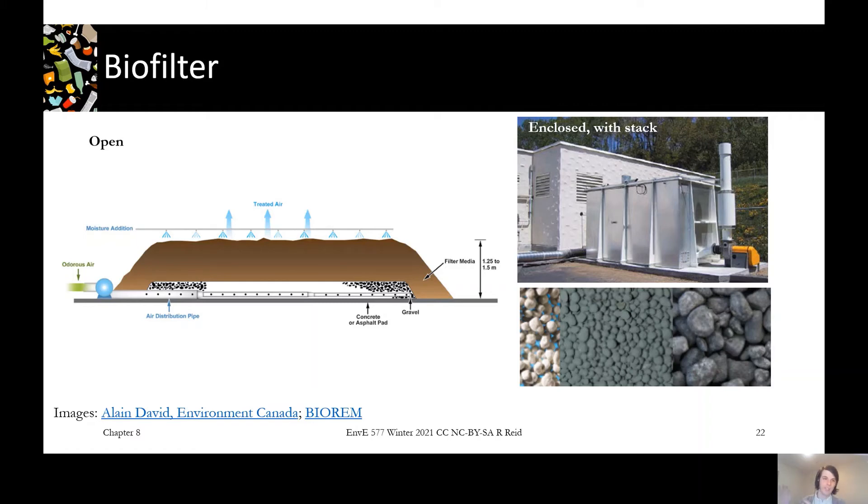There are more high-tech and more low-tech options of biofilters. On the left is a more low-tech one which is literally just a pile of wood chips as the media over a distribution pipe that's bringing the odorous air in and then there's some nozzles to help keep it wet. So this would just look like a windrow with positive aeration but it's specifically there to keep growing those microbes that are going to eat up your odour compounds. There's also more high-tech looking ones like the one on the right. This one is fully enclosed. This one has a little blower and a stack on it. There's ones with way higher stacks like 30 meters and more.